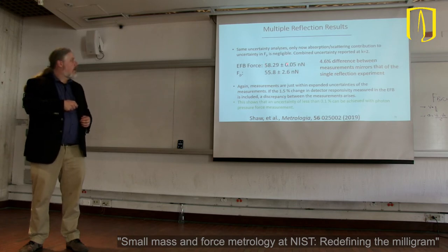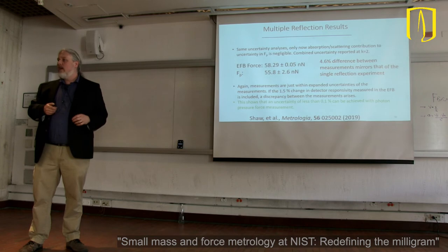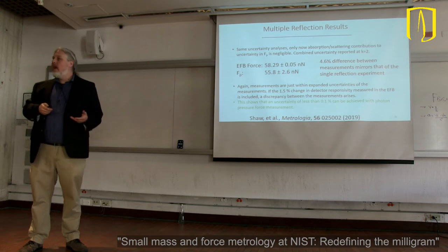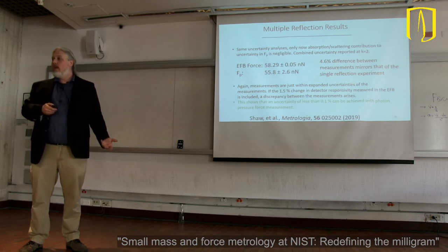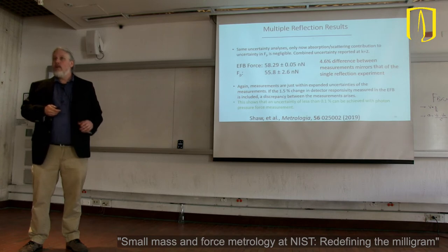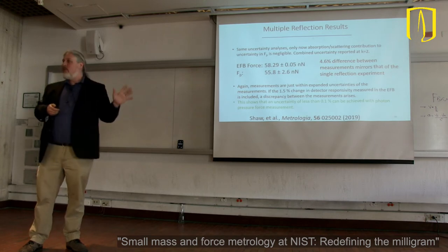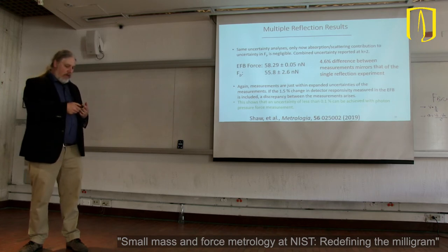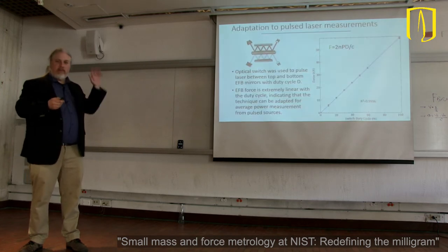right? We get less than a 0.1% uncertainty in our measurement. And so this is potentially good enough to improve the laser power calibration in a watt by two orders of magnitude in terms of the uncertainty. So that is actually potentially a large improvement for the state of the art. We have a paper on this also, in case you're interested.